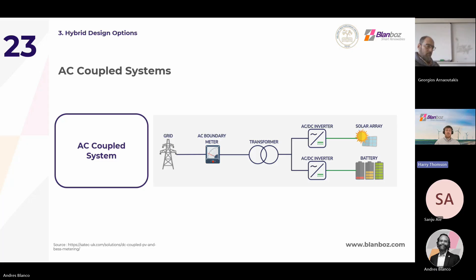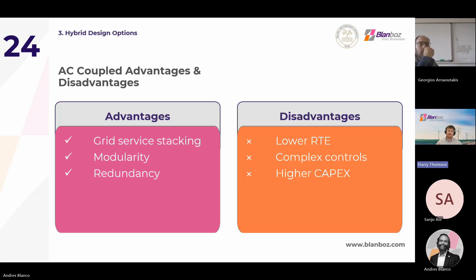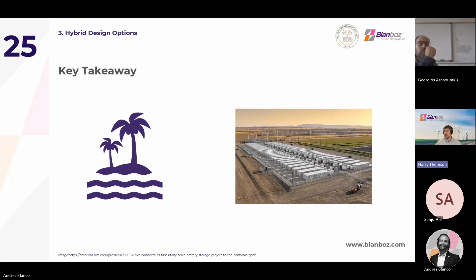And there's also a higher capex. There's more equipment to purchase, and you have the more complex control system, which all adds up, and all needs to be considered when designing the site. So the key takeaway from this is that it's project specific, and it depends on how the battery is planned to be operated. Are you building a small 2 megawatt, 4 megawatt hour BESS on a remote island that's being used to maximize solar production during the day? Or is it a large 500 megawatt, 1 gigawatt hour BESS that's supporting grid functions and maximizing revenues? The use case depends on the coupling system, and that impacts the design decision.